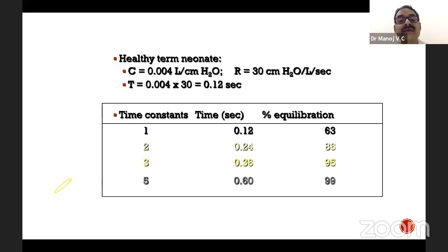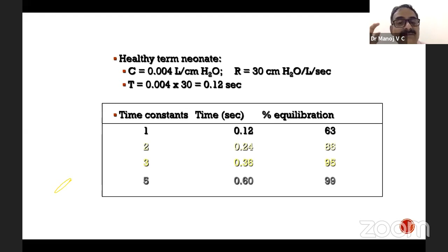And what is it that you are getting? You are getting 99% of flow. Whereas you can get an equivalent value, 95% of equilibrium, with 0.36 seconds. So much time you can save for preventing air trapping and allowing the baby to expire, and give enough time so that there is some leverage to increase the respiratory rate as well. So in practice, we use 3 time constants as the time set for inspiratory time. This value will differ depending on the pathophysiology. 0.36 is probably ideal for a term neonate, but this value will be different in different disease pathology. But then you know where you stand.